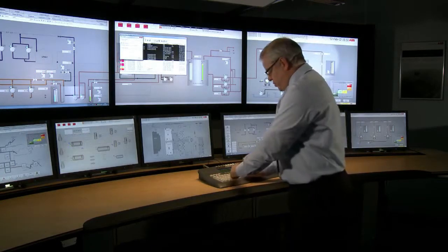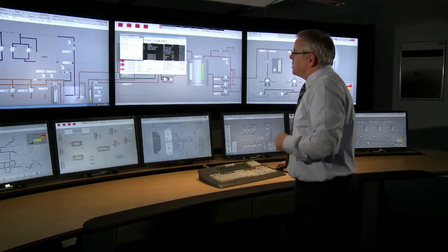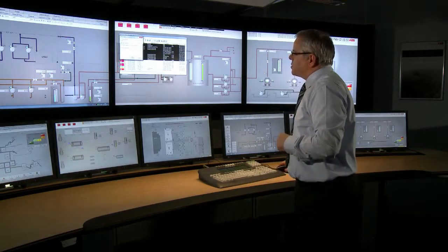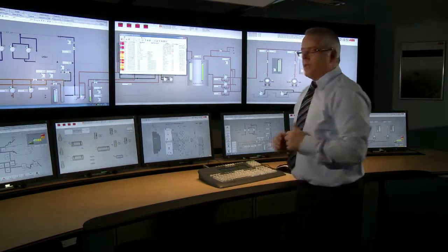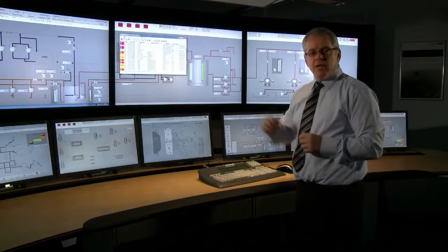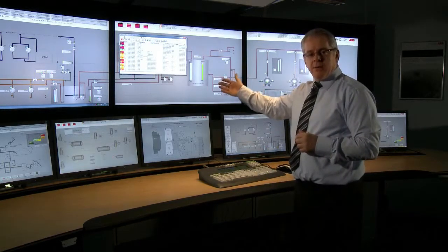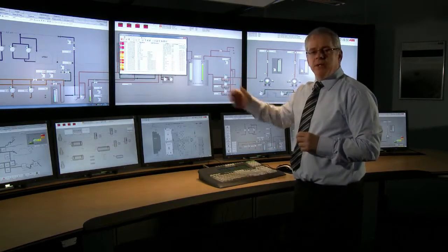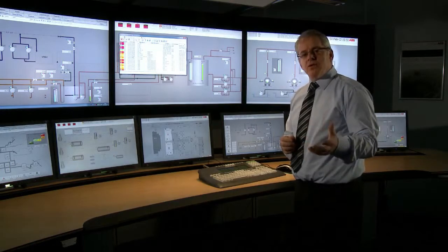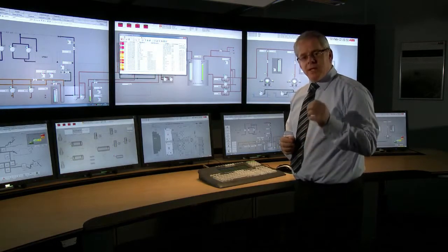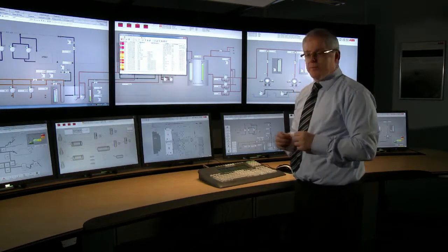After entering the reason for shelving those alarms and selecting OK, those alarms become shelved. They will no longer enunciate on the alarm list for the period that they are shelved, meaning they're not contributing to the KPI statistics on the alarm management system.